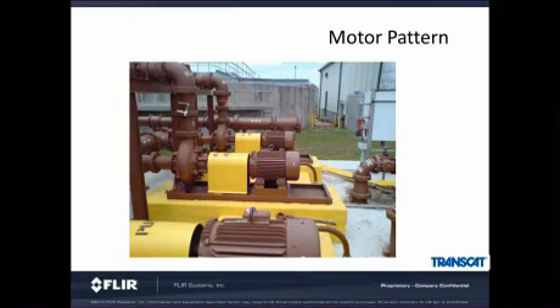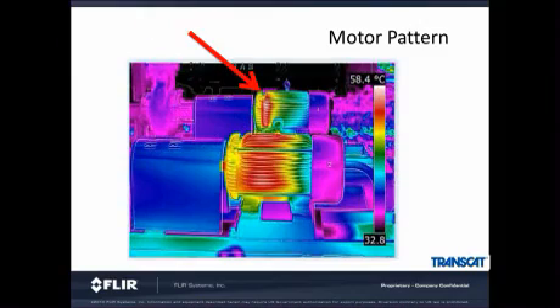We keep continually talking about comparison images, and this one is no different. The difference in temperature between these two objects is very clear and would not have been picked up by a spot gun. Both motors are the same model doing the same exact work. And I have to emphasize, when you're looking at motors, bearings, gearboxes or pumps, unless you have a database of these targets, you need to be looking at motors and gearboxes and bearings doing the same amount of work and being from the same manufacturer and being the same model. Because if they're not, you will not be getting the full value of what the camera can do. So in this case, we can clearly see that the motor in the background has localized hotspots.